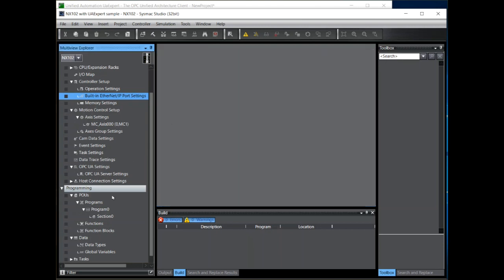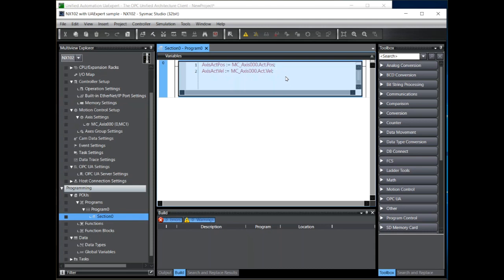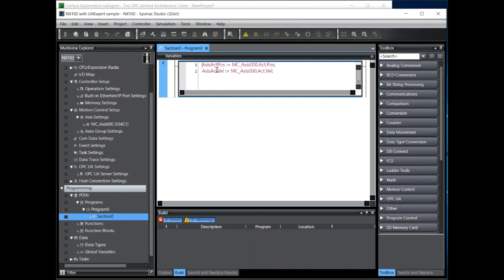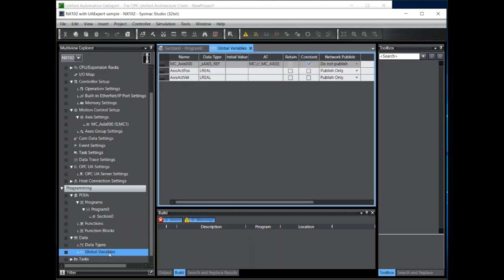I have a simple program here where I'm picking up actual position and velocity of a servo and copying these to two variables which will be read by the OPC client. Two important notes about these variables. Firstly, for OPC UA clients to see them they must be defined as global and they must be defined as publish.